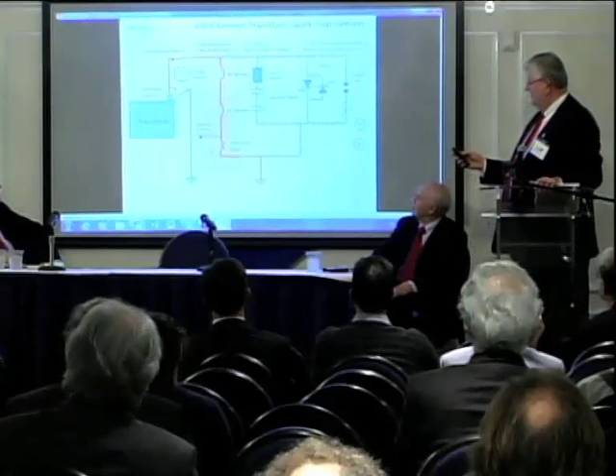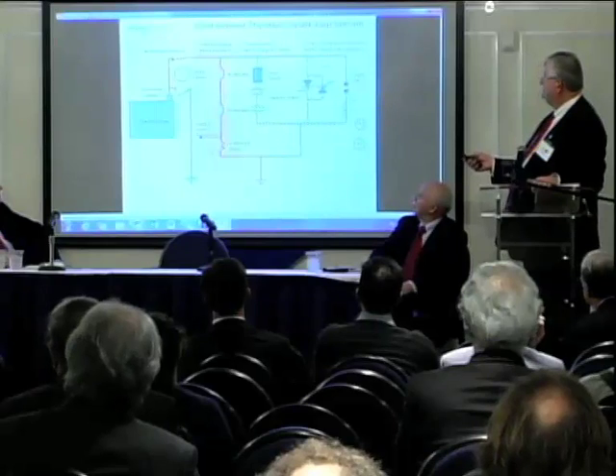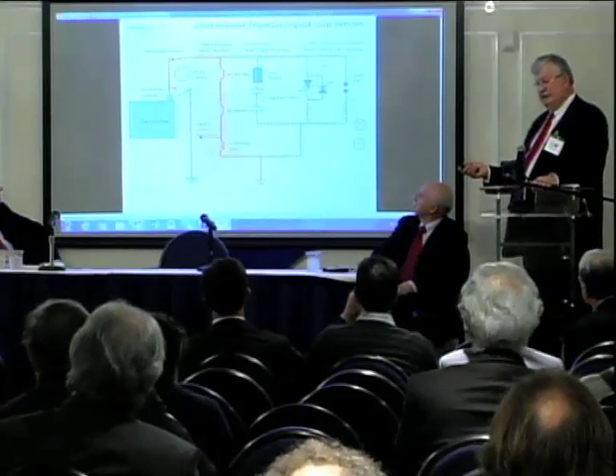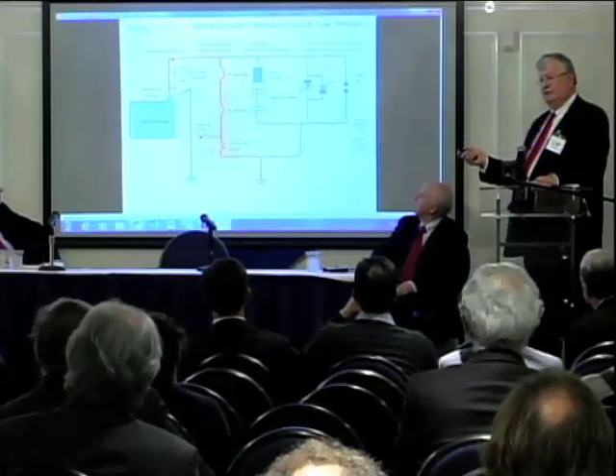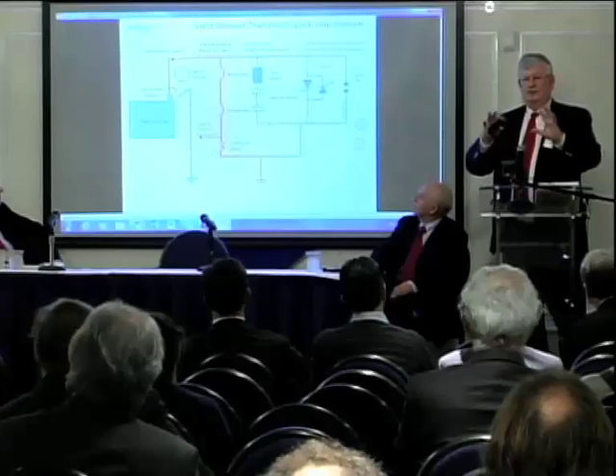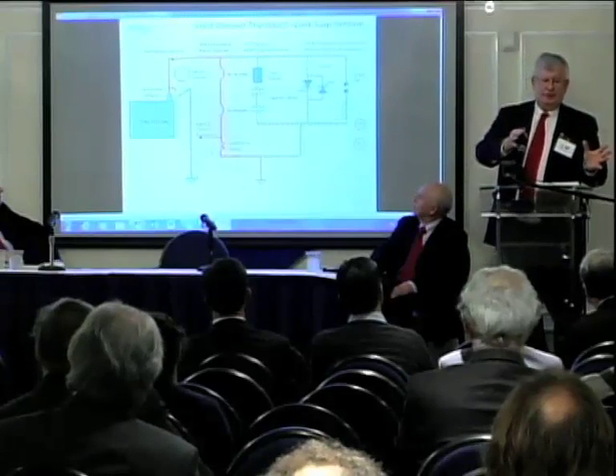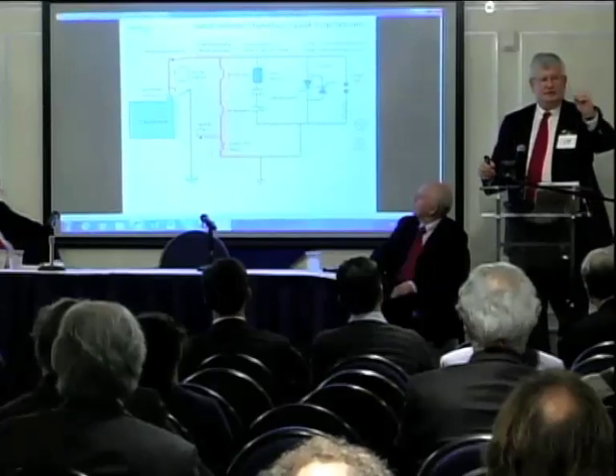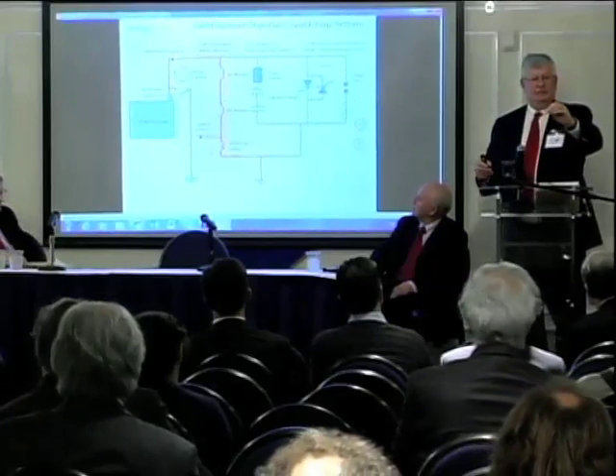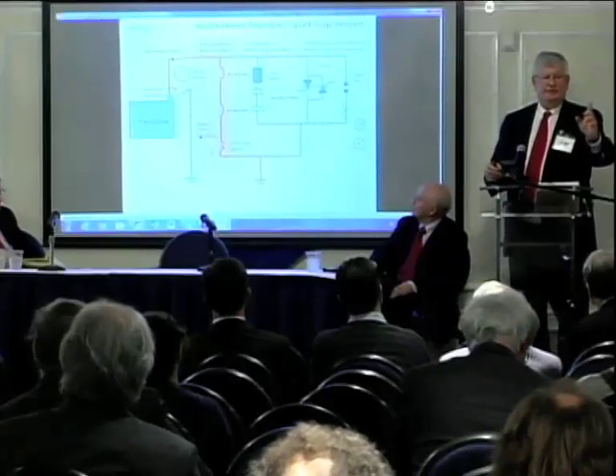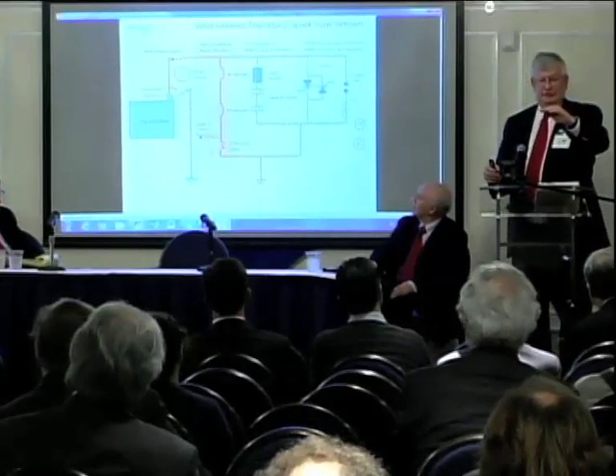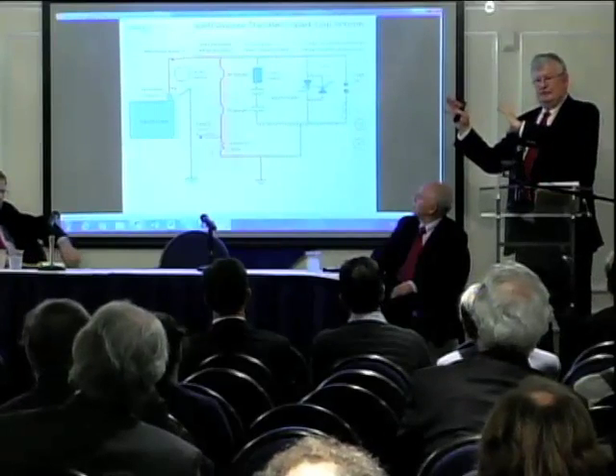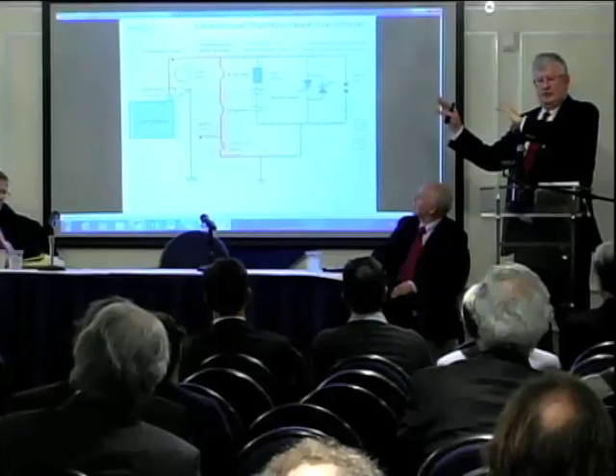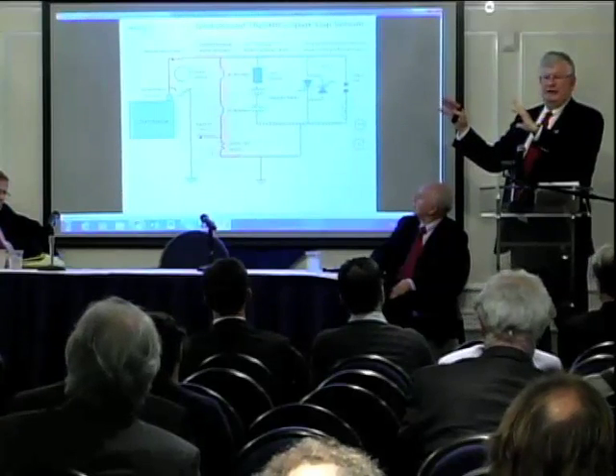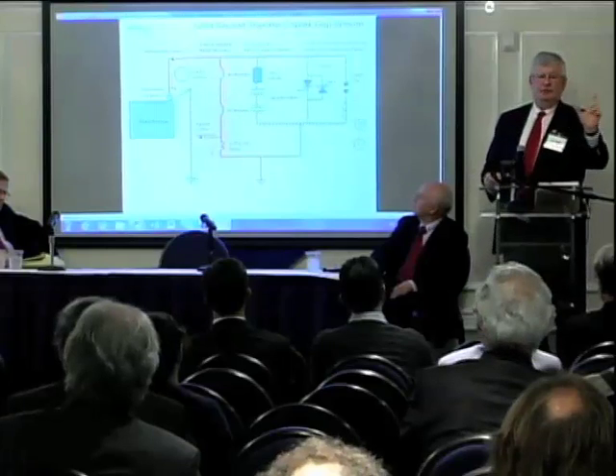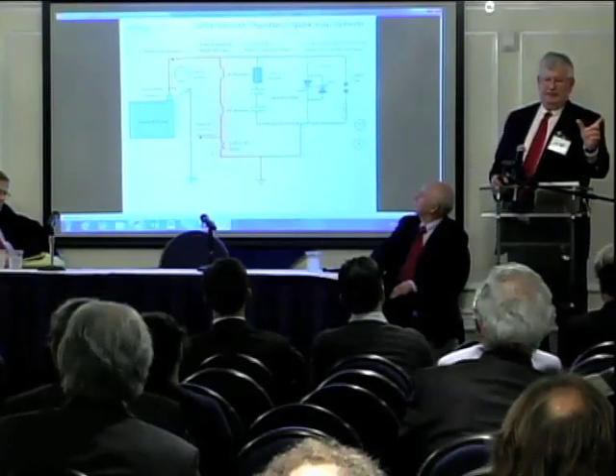So we've come up with an even beefier system. When we did some testing, we found, in modeling, we found that in the Wisconsin grid, at the 100-year storm level, we checked the voltage level at every single substation, and with one exception, the highest that it was at was 2,000 volts. The first model that we had was capable of operating at 4,000 volts, but there was one long line, 150 kilometer line.